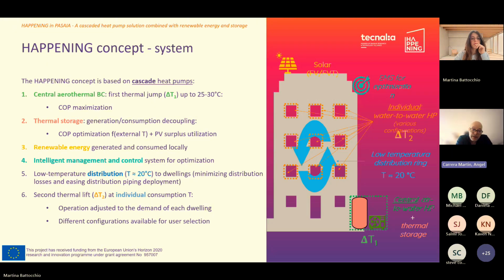The distribution loop runs at 20 degrees at each dwelling to minimize distribution losses, but this also allows the use of cheap flexible plastic pipes that can be installed more easily than traditional distribution systems. Each building has an individual heat pump, which makes a second temperature lift from this 20 degrees to the temperature needed for domestic hot water production or space heating demands.